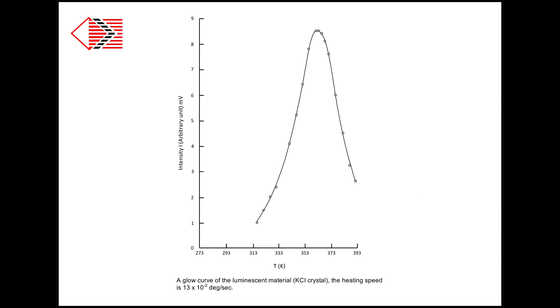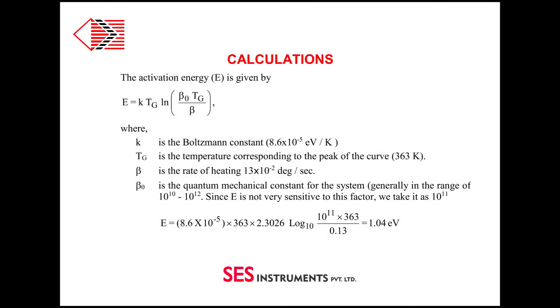The plot of these readings, intensity versus temperature, will give us a glow curve. The glow curve gives us the value of transition temperature Tg. Putting this Tg in formula, we can get activation energy E. Details are given in our user's manual.